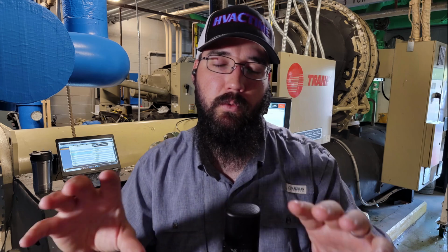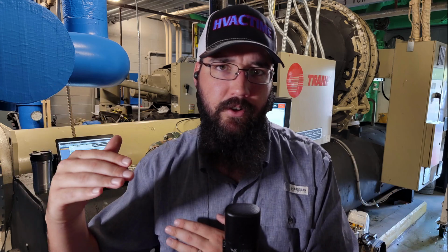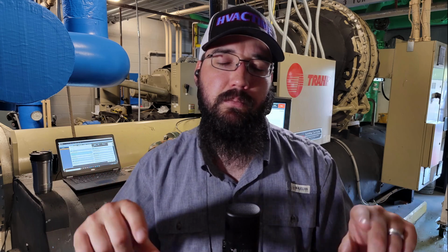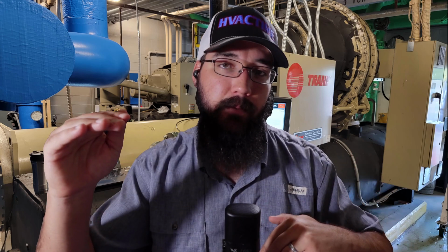So yes, on some of those larger air cooleds, and we are talking about typically screws, when we have to start splitting circuits, that is what they'll do. Instead of putting a large, expensive 100-ton, 150-ton valve in there, they'll split that between, say, two 50-ton valves or two 60-ton valves. Maybe they'll upsize them just a little bit, and those two valves now need to be synchronized and be able to work together. So that, again, is part of the complexity when you split two different heads like that. It is best for them to be synchronized in order to get a balanced flow through them. Otherwise, you can start creating load issues.